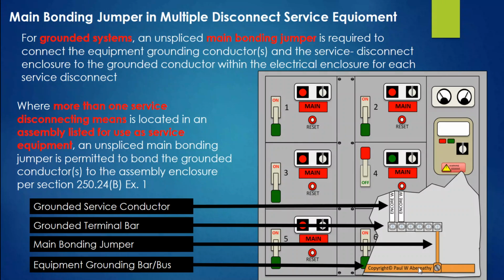And what you'll have is a common location where you'll have a grounded equipment grounding bus that runs along the bottom of the equipment. It's just a common location that's common to all of these disconnects. And then what you'll have is the main bonding jumper that connects, just like you would in a regular panel system, the grounded terminal bus over to the equipment grounding bus. And that would be your main bonding jumper. And of course, we have to size that, because it is of a wire type based on the size of the service entrance conductors that are supplying this equipment. And then again, here are the grounded service conductors coming in as well.